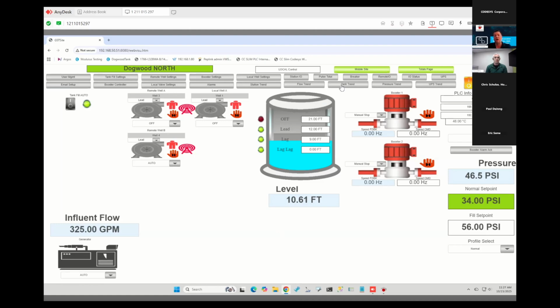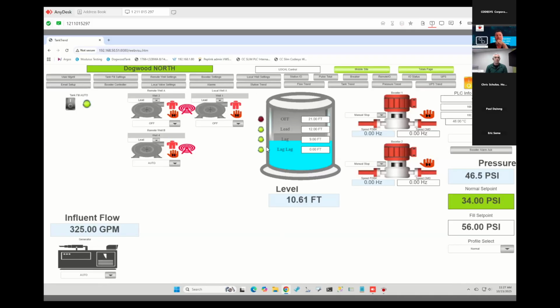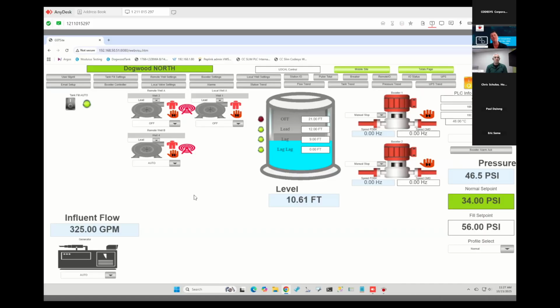And we're doing all the trending here too. So you've got your tank trend. Here you know if the wells are running, if the valves are open. And then we have anything with the pressure trending. So what the speed of the VFD is, what our pressure set point is, and what our PID output is. So that's important to know, because we want to know, is the PID tuning up and the drive's not following? Is it running too fast?